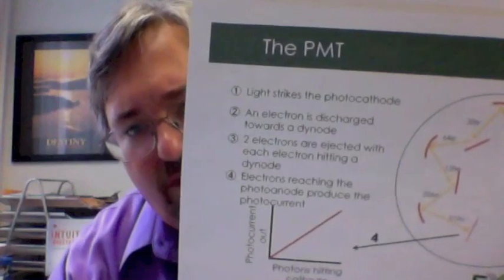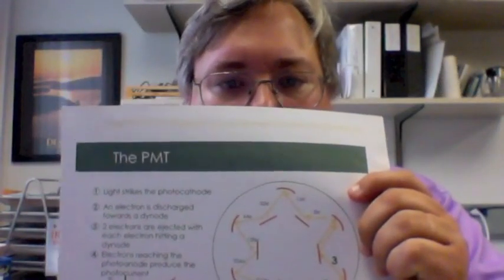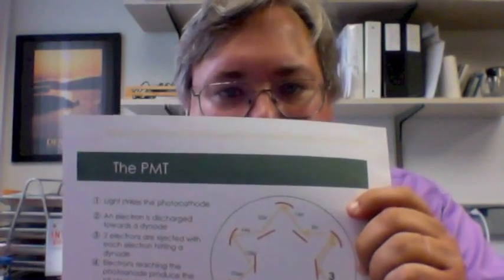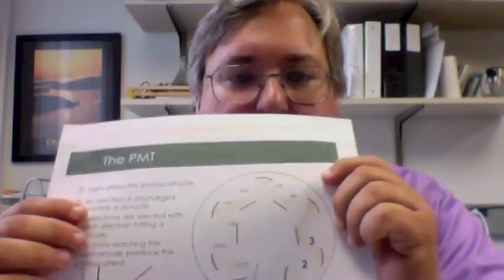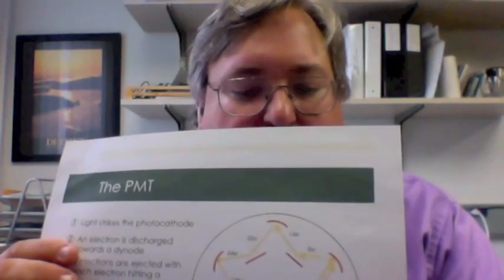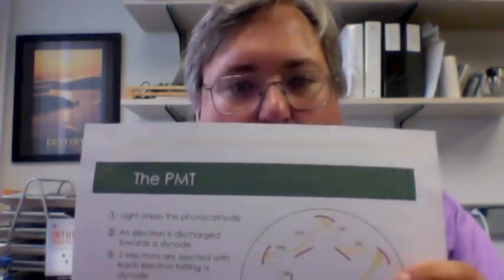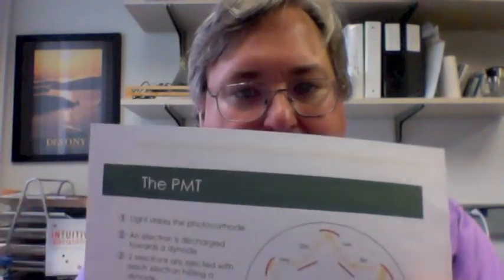Here is a cross-section diagram of a photomultiplier tube. We've cut the photomultiplier tube down, and here we have it shown. As light hits the inside — hits the photocathode right here — if it's of sufficient work energy, it will eject an electron. That electron speeds over to this dynode. The dynode is under slightly higher voltage, and as the electron hits that dynode, it is amplified. Two electrons get shot out to the next dynode, then four to the next, then eight, and so on and so forth. So as we go through this whole chain, we're amplifying one photon of light into many, many electrons.